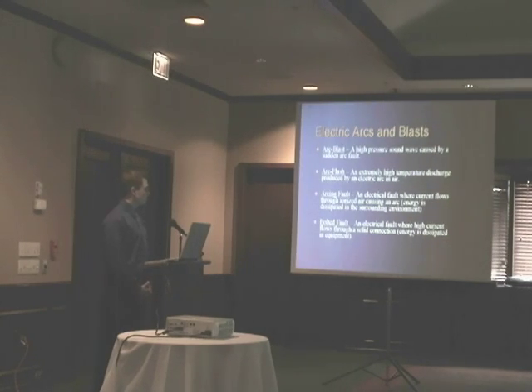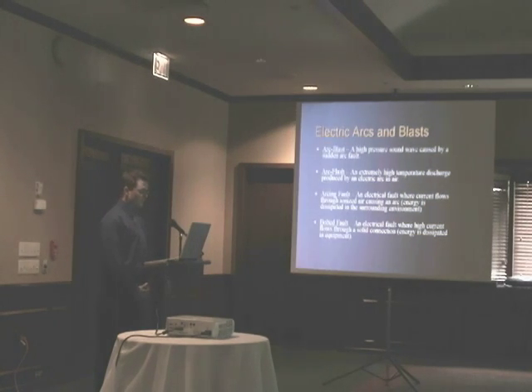Okay, a little bit of vocabulary here before we get into the meat of this. An electric blast is a high pressure sound wave caused by a sudden arc fault. An arc flash is an extremely high temperature discharge produced by an electric arc in the air. Now, there are two different kinds of faults that can cause an arc flash and an arc blast. An arcing fault is an electrical fault where current flows through ionized air, causing an arc. This is when the energy is dissipated in the surrounding environment. And then a bolted fault is where an electrical fault flows through a solid connection. This is where the energy is dissipated in equipment. Or if you were working on equipment and you happen to drop a wrench or something on a bus bar, this could cause a bolted fault. The arcing fault can be caused, in a steel mill, where you have a lot of particles in the air that the arc can flow through to cause an arcing fault.